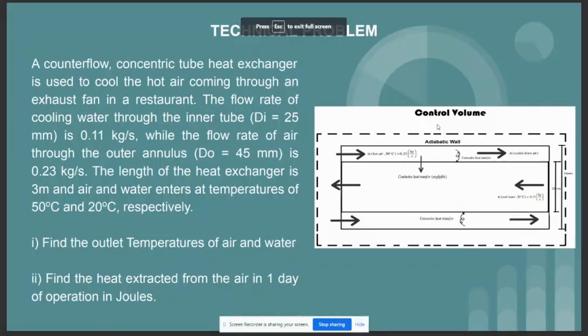Hello, my name is Sharnam Faria. I'll be explaining the following parts. First, the technical problem. A counterflow concentric tube heat exchanger is used to cool the hot air coming through an exhaust fan in the restaurant. The flow rate of the cooling water through the inner tube is 0.11 kilograms per second, while the flow rate of the air through the outer annulus is 0.23 kilograms per second.